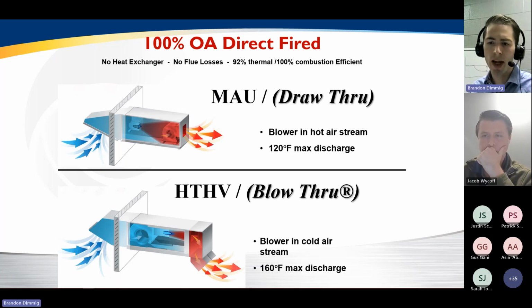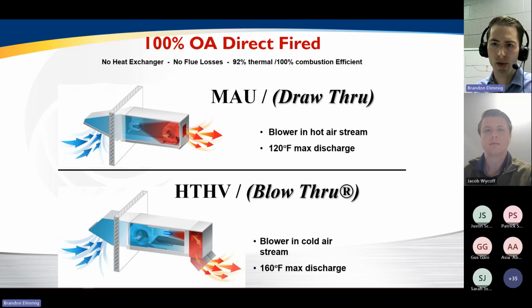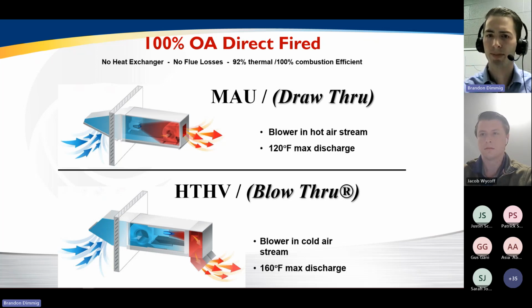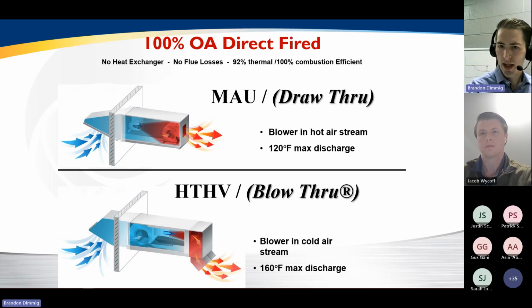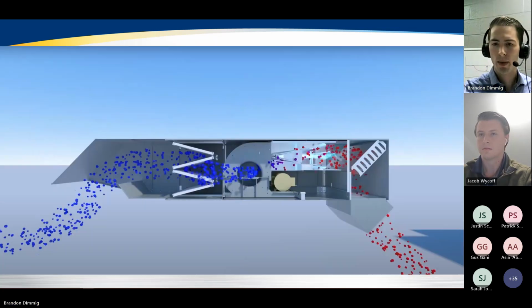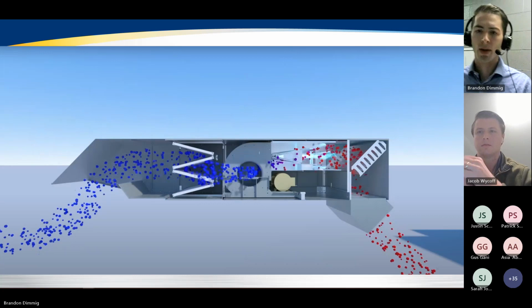It's an important one, and it's what allows the discharge temperature of an HTHV unit to get as high as practically possible. And that, in conjunction with the proprietary nature of the burner, allows you to hit 160 degrees on the discharge temperature. So again, in both of these, there's no heat exchanger losses, there's no flue losses, but that orientation difference does have a big role in these units in general.